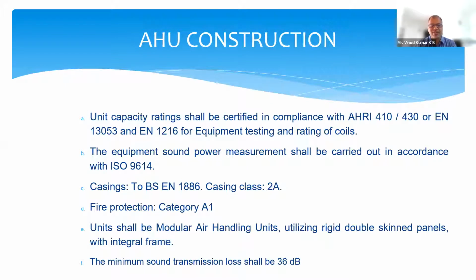Similarly, the fire protection category, we categorize it as A1. All the air handlers that we use in a hospital should be double-skinned air handlers. Double-skinned in the sense that the casing will have an outer casing and an inner casing, and in between the two casings you have insulation. This insulation is actually going to control the heat transfer from outside to inside, and thereby help you to maintain your temperatures for the respective areas where the AHU is feeding. At the same time, it will help control condensation on the air handler. So you can imagine that there are many places where the AHUs do not have a double-skin casing. It's just a single skin. With a single skin, there is a lot of energy loss. There is going to be temperature loss as well as condensation, which is going to be a perennial headache for the organization. So the criterion is that you need to have a double-skin AHU.